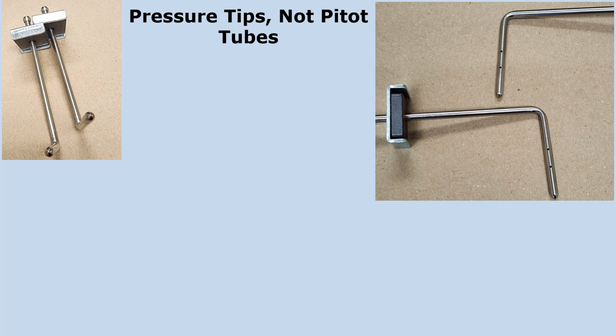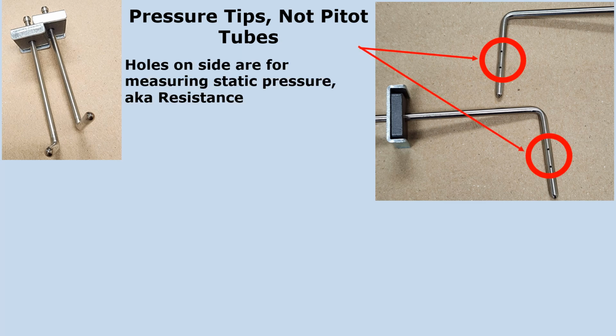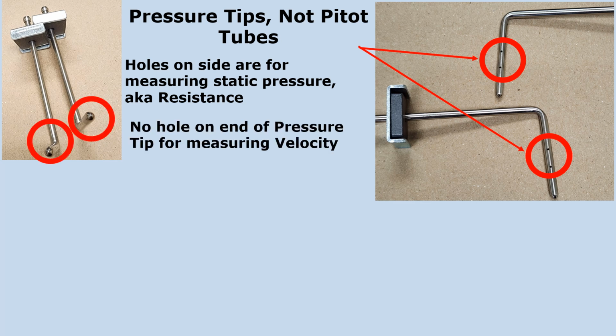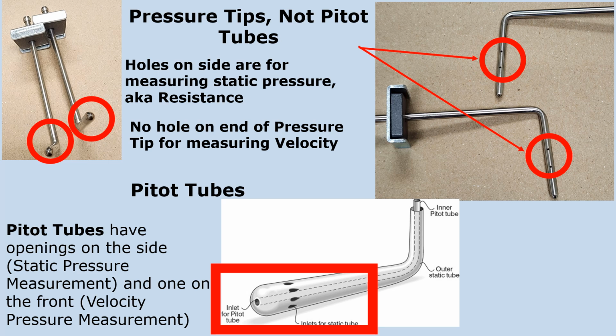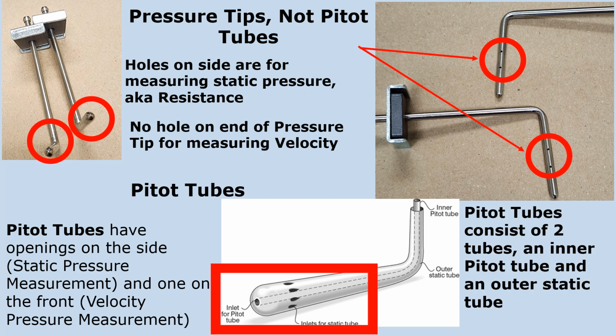Pressure tips, not pitot tubes. Holes on the sides are for measuring static pressure, aka resistance. No hole on the end of the pressure tip for measuring velocity. A pitot tube does have that. As you see here, pitot tubes have the openings on the side for static pressure measurement, and one on the front for velocity pressure measurement. Pitot tubes consist of two tubes, an inner pitot tube and an outer static tube.